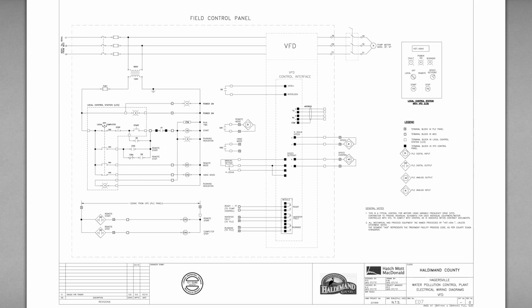They are used to connect to motors to run them at different speeds. When we were talking earlier about a Hertz meter, Hertz would just measure the frequency in cycles per second of a device. If you need to run a pump at a specific RPM, you could scale this pump to run at a specific frequency, and you would have to do some math to match the frequency with its speed based on the pump rating. So that was a mouthful. If anybody has a question about that, I can repeat it.